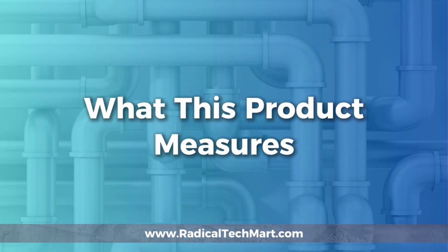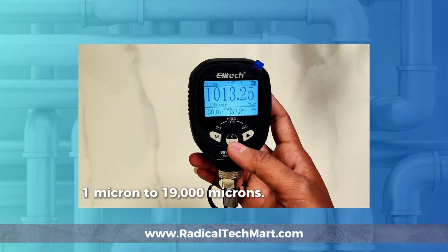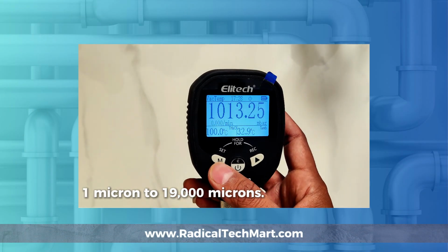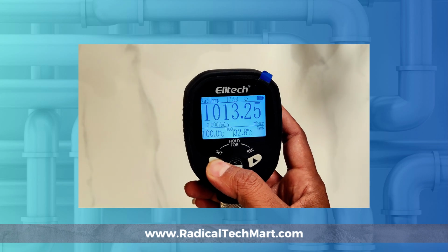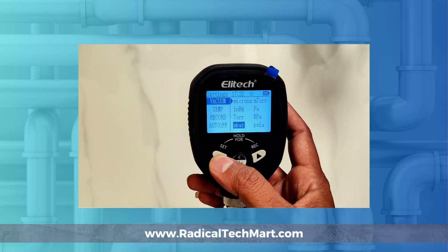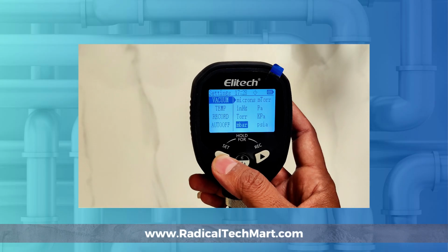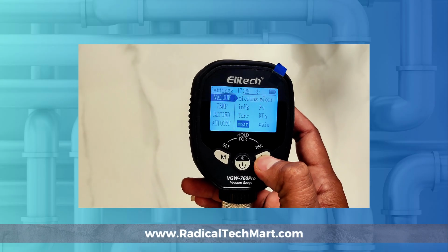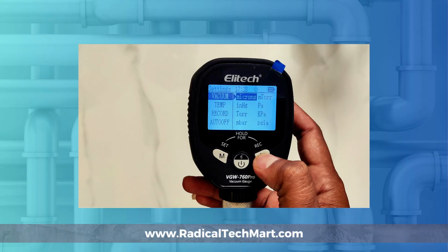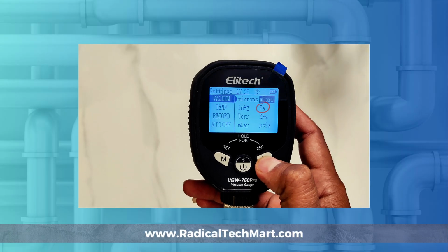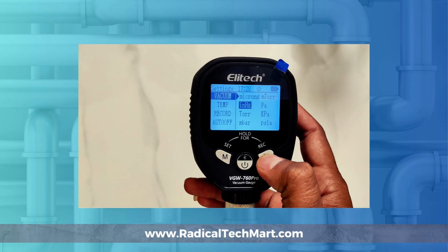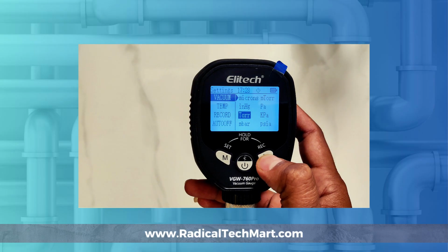The VGW-760 measures vacuum pressure. Its measuring range is from 1 micron to 19,000 microns. In HVAC work, micron is commonly used to check vacuum level. Lower micron value means deeper vacuum. The gauge also supports different units like micron, Pa, mTorr, Torr, mbar, psi, inHg, and kPa. So the user can select the unit as per requirement.